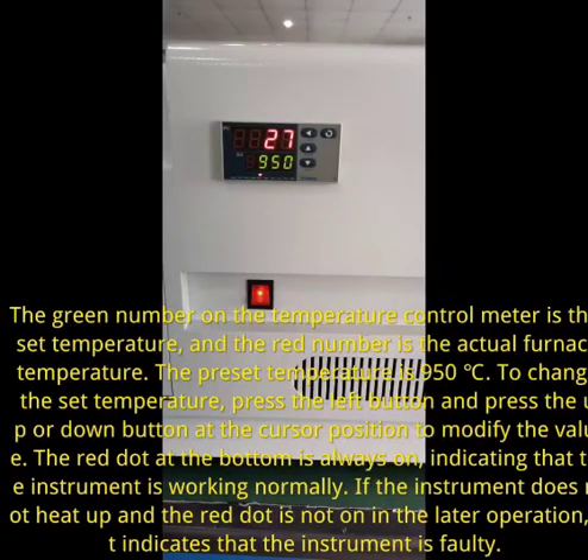The green number on the temperature control meter is the set temperature, and the red number is the actual furnace temperature. The preset temperature is 950. To change the set temperature, Press the left button and press the up or down button at the cursor position to modify the value. The red dot at the bottom is always on, indicating that the instrument is working normally. If the instrument does not heat up and the red dot is not on in the later operation, it indicates that the instrument is faulty.